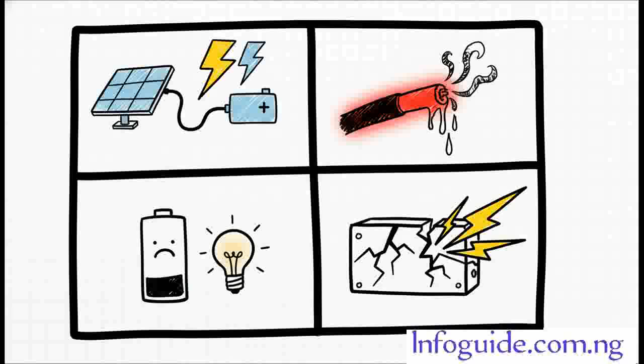And that electrical traffic jam has some pretty nasty real-world consequences. First up, voltage drop. This basically means the power that leaves your panels never fully makes it to your batteries. You're just losing it along the way. Second, and this is the really scary part, all that congestion creates a ton of heat. I'm talking melt-the-insulation, create-a-fire-risk kind of heat. It all adds up to a huge loss of power and can even permanently damage your expensive equipment.